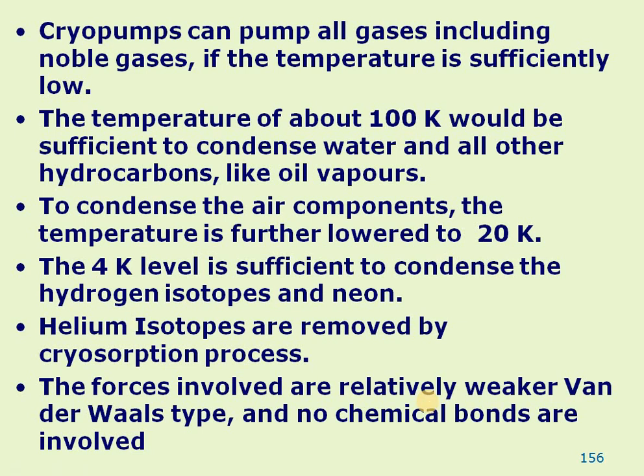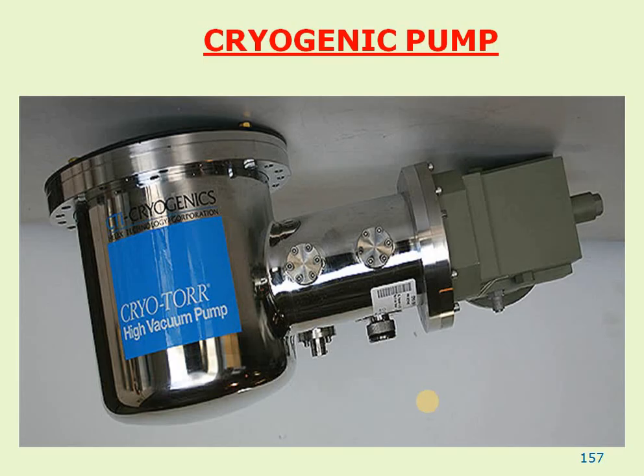One advantage is that when you want to remove all these deposited gases, you simply increase the temperature inside the chamber. When you increase the temperature, each gas and vapor condensed on the surface gets sublimated or evaporated at different stages, and this way all the gases can be removed.